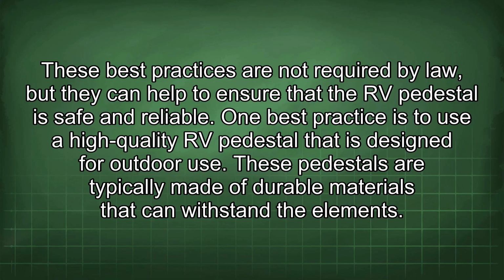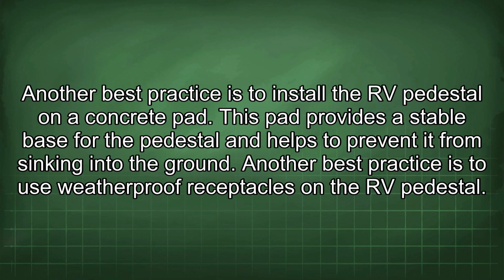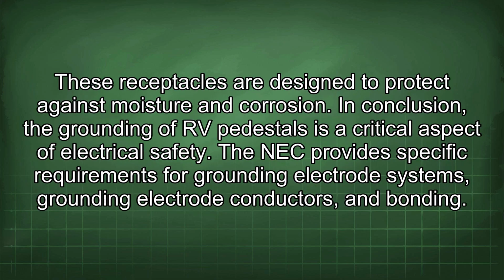These pedestals are typically made of durable materials that can withstand the elements. Another best practice is to install the RV pedestal on a concrete pad. This pad provides a stable base for the pedestal and helps to prevent it from sinking into the ground. Another best practice is to use weatherproof receptacles on the RV pedestal. These receptacles are designed to protect against moisture and corrosion.